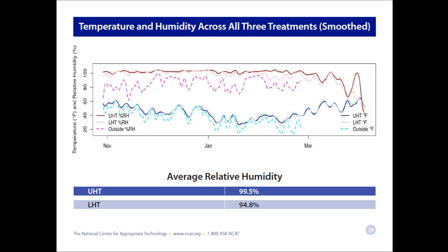Actually, all of the data we collected, we put into graphs that you can see here. And to answer the first question that I set out to answer, to see if the heat exchanger would control the moisture or the relative humidity in the high tunnel, we graph that in the three lines on the top of this graph. And you can see that the solid pink line, which represents the lower high tunnel that had the heat recovery ventilator in it, actually drops below the upper high tunnel relative humidity quite a bit throughout the season. So it definitely was lower. The relative humidity was lowered in the tunnel with the heat recovery ventilator in it.